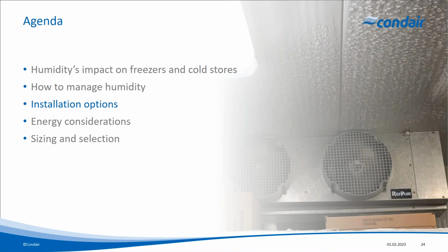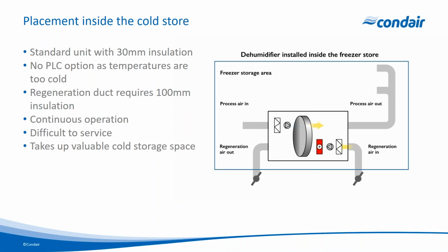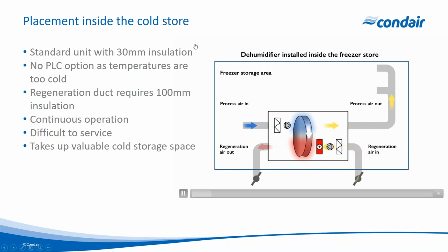Okay, so what are the options? Well, we then start to look at what kind of application you're looking at. Where are we going to put the dehumidifier? So on these slides, if I draw your eye to the right-hand side, we've got a blue box here, and this blue box represents your freezer store. And here we've got a dehumidifier that's installed inside the freezer store. So air is going to be brought in over a filter, inside the dehumidifier, over a fan, and then pushed over the desiccant wheel. And that desiccant wheel is going to capture that moisture. So we then have dry air coming back and into the freezer. Nice and straightforward. Units coming in, over the rotor, and then out again.